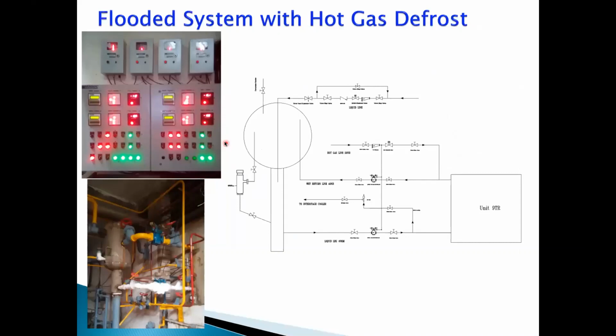Now, when we are running these cold storages, particularly at very low temperatures, right from 0 degrees to minus 40, whenever these plants are running at low temperature there is always an ingress of air when the doors are operated, with frequent operation of doors during loading and unloading of the cold rooms. The moisture in that air accumulates on the evaporator coil and becomes frost. Frost is nothing but ice, and as we all know, ice is a bad conductor of heat. So when frosting happens on a coil, the main function of the evaporator coil, which is heat transfer, reduces and then stops.